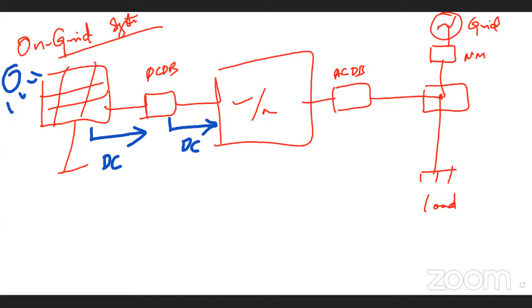So now it's AC, and this AC goes to the ACDB, then from there to the LT panel. Once it reaches the LT panel, it has two options: either it goes to the load, or it goes to the grid. That depends on whether there are any local loads at that point. If there is a load, it goes there; if there's no load, it gets exported to the grid. If it goes to the load, this condition is called captive consumption.